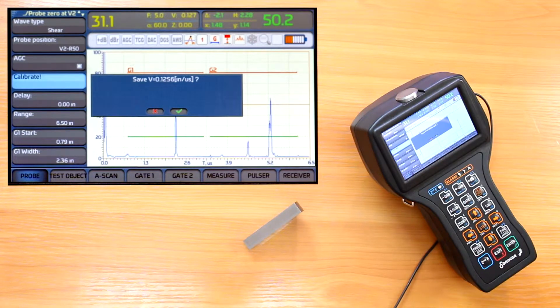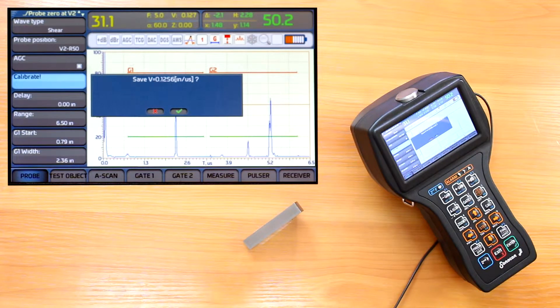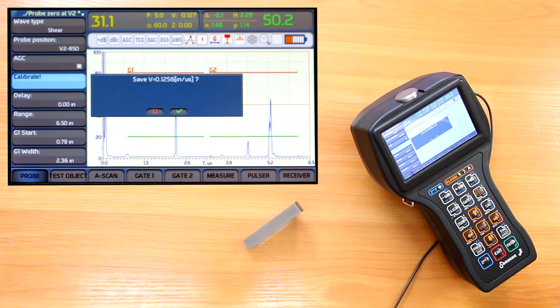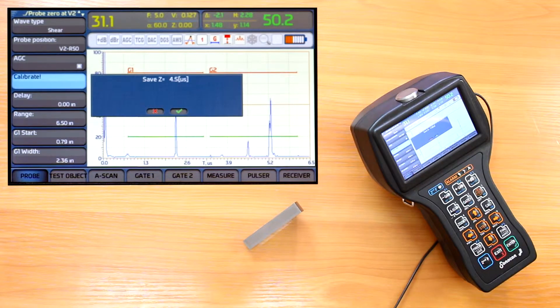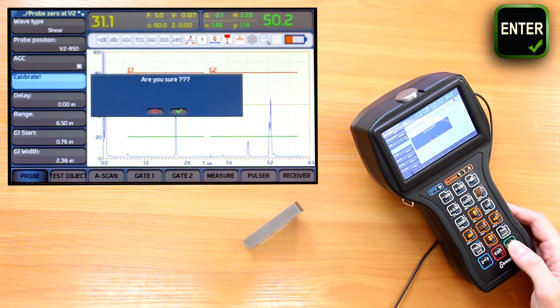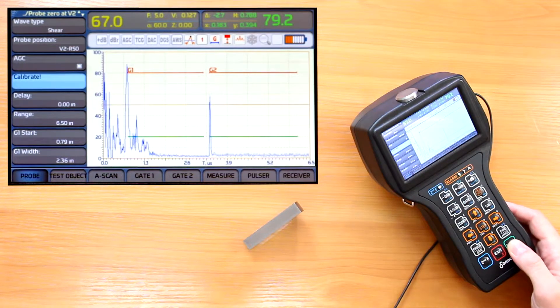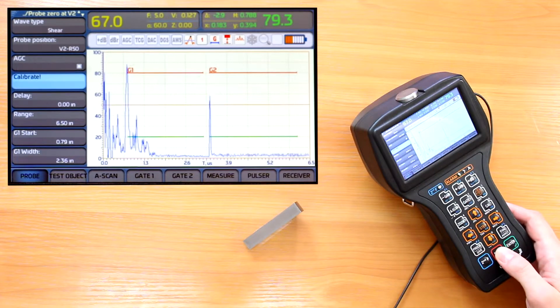It then asks if we wish to save the calibrated value of sound velocity. If we used a V2 made from the same material as the test piece, it's a good idea to save this velocity by pressing enter and confirming again. The same question is asked about the probe zero value, so we press enter twice to confirm it as well. The exit button takes us back to the choice of calibration procedures using standards.